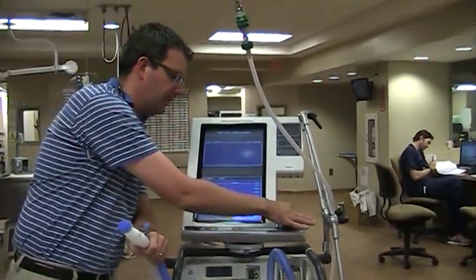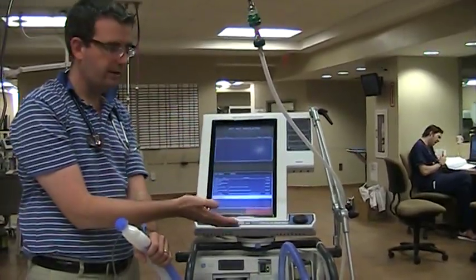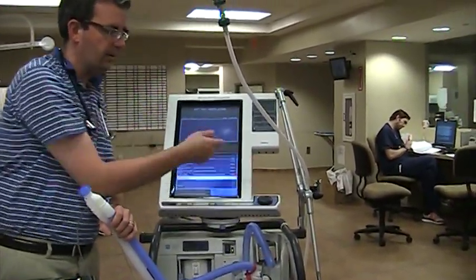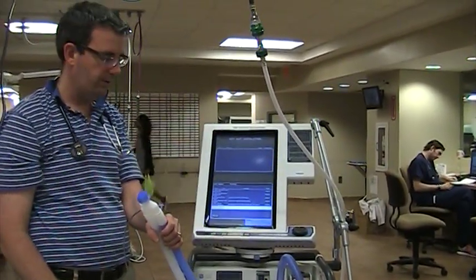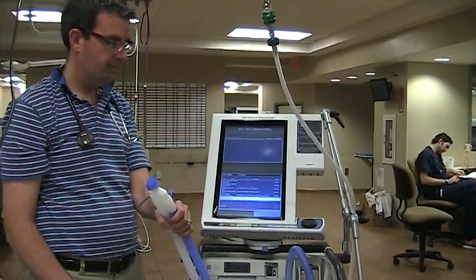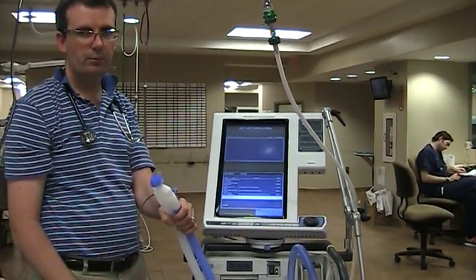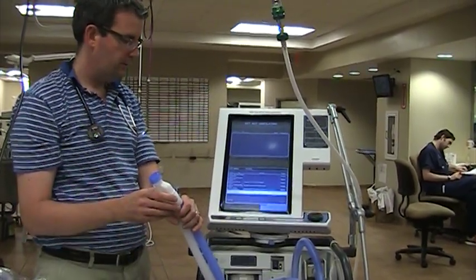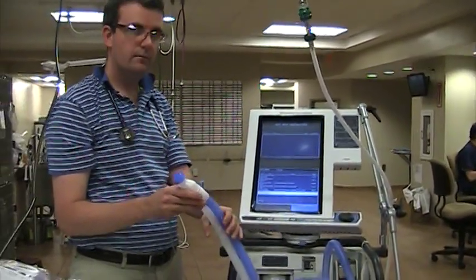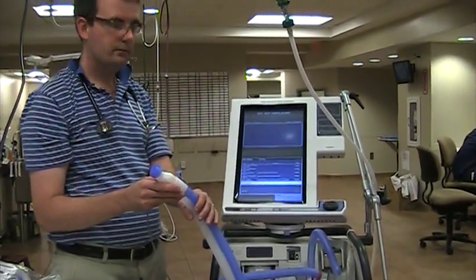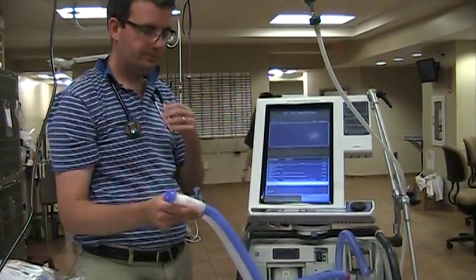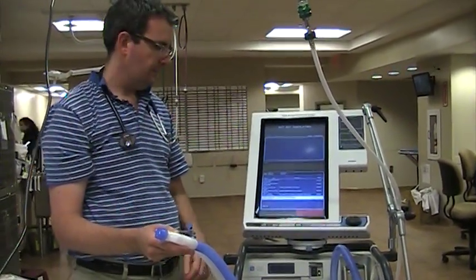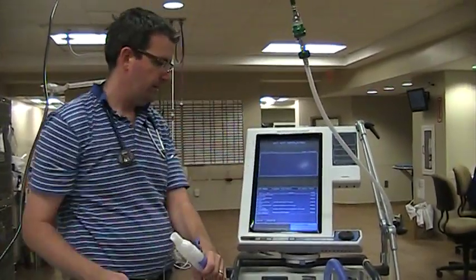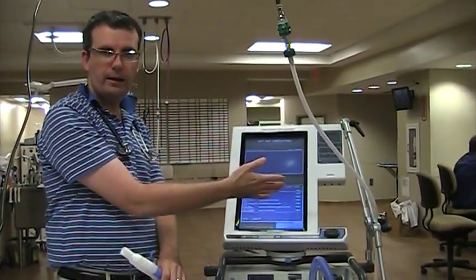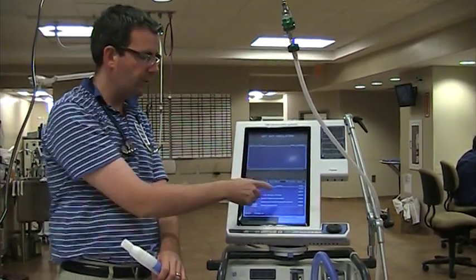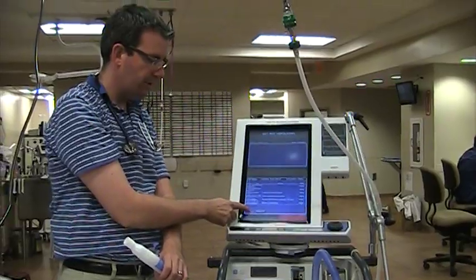Now it says block the Y, press accept. Is there water in the humidifier? Normally you would say yes, but in this circumstance there's none. So we press clear. Press accept if there was water in the humidifier. It's just doing a compliance calibration right now. It says unblock the Y, press accept, and now it's ready to go. If you failed something and you wanted to go back and retest it, you would say restart SST, but because we passed everything, we're going to press exit, press accept.